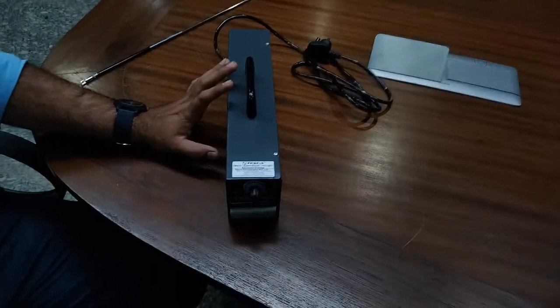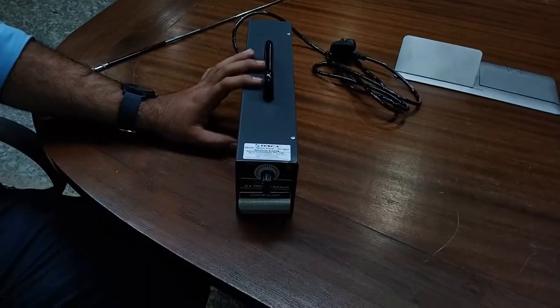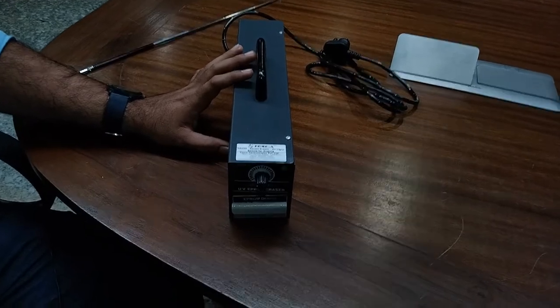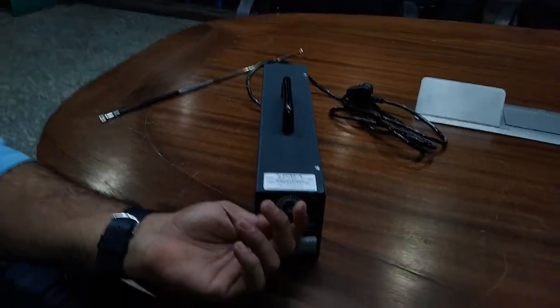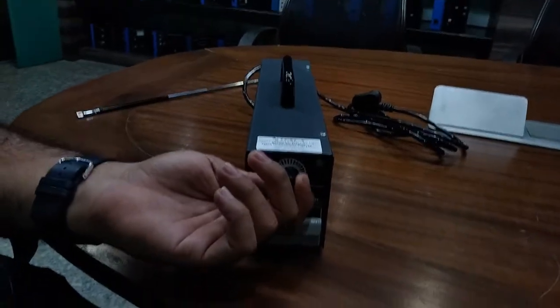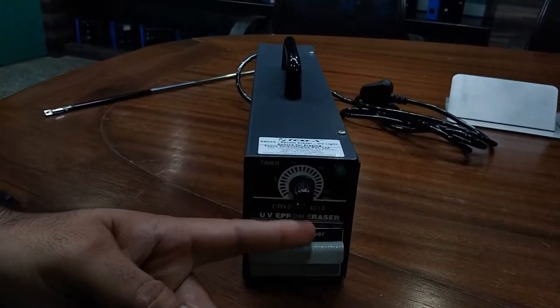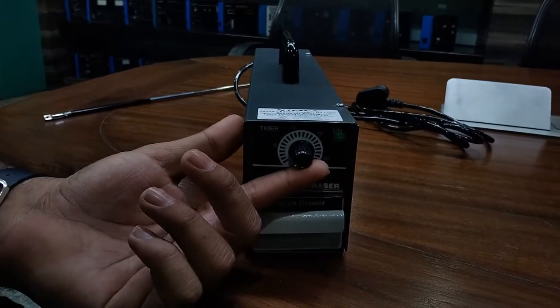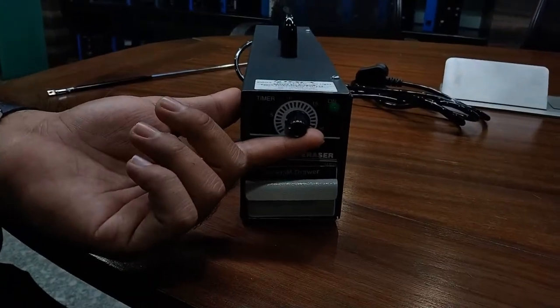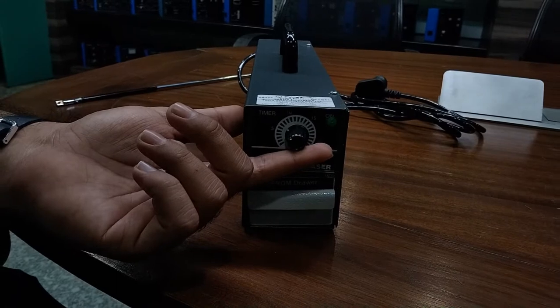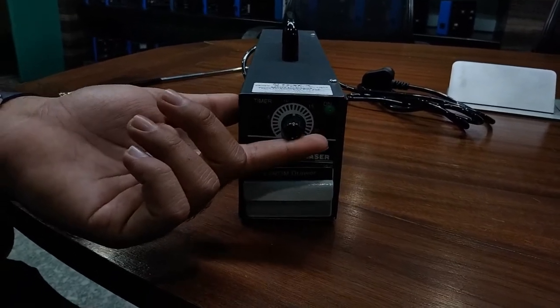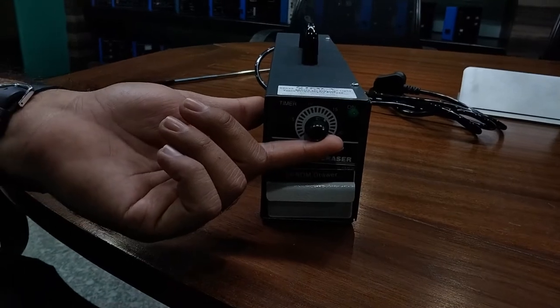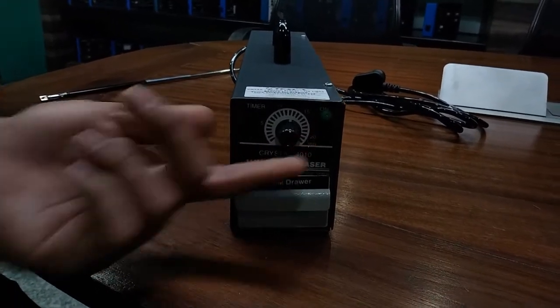The approximate life of the UV lamp is about 500 hours and the electronic timer can be set from 0 to 22 minutes in different steps. You can place the timer per 1 minute from 2 to 22 in different steps for timing range. The accuracy of timer is plus minus 10 percent.